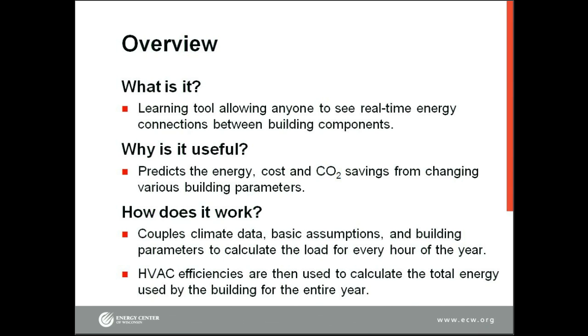The calculator works by coupling location-specific climate data, such as what the temperature is outside, a few simplifying assumptions — which are all listed on the website — and a list of design inputs to calculate the building's load for every hour of the year. The HVAC efficiencies are then used to calculate how much energy this load entails. From there, we use a simple equation to calculate the building's annual cost and CO2 emissions.